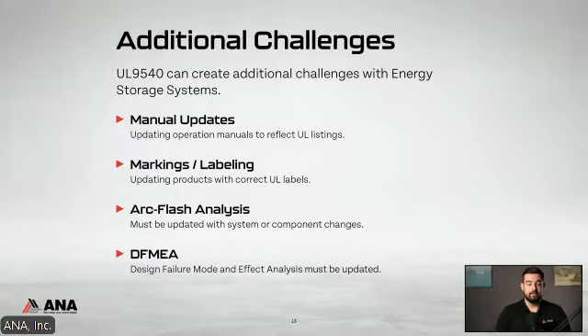DFMEA, design failure mode and effects analysis. So, this is a fancy analysis that basically says if a fault were to occur, what happens, right? So, it'll go through what kind of injuries can happen, what kind of damage to the equipment can happen, and both its severity as well. So, based on your severity level, you may need to tweak the design a little bit. There are third parties that can come in and do a DFMEA for you, but yeah, this is going to be a required piece of the standard.